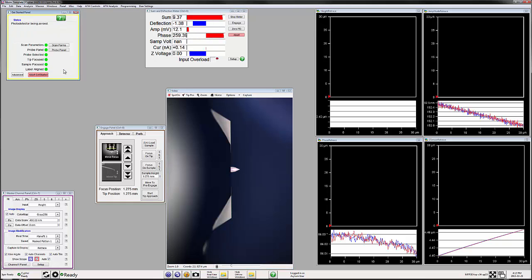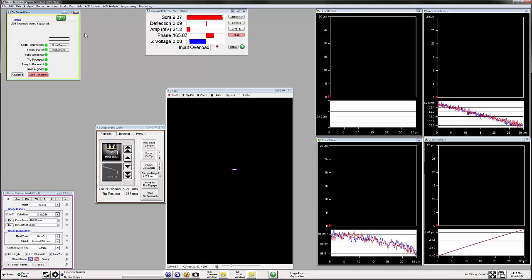The first thing that will happen is a GetReal calibration, where we calibrate the sensitivity and stiffness of the cantilever without having to touch it against a surface. This procedure will take several thermal spectra of the cantilever's fundamental frequency and fits its F0 and Q. From there, we can determine the spring constant of the cantilever using some models. Once the spring constant is calculated, we can use the thermal tune to calculate the cantilever sensitivity, all without engaging the tip onto the sample.